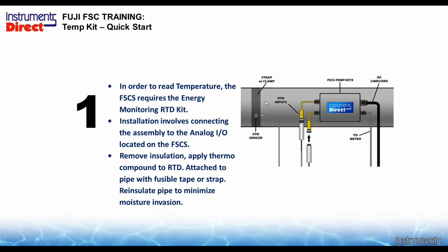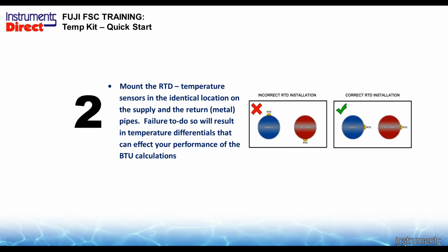So in this case here, we would give you the strap-on RTD, and then the thermo compound, kind of like a zinc oxide, to transfer this RTD temperature from the pipe surface itself for a metallic pipe application. And you put this on the pipe with a fusible tape. It's like a flexible duct tape that bonds to itself there, which stays there forever, or you can just use a hose clamp, whatever's convenient for you. So there's one on the supply, one on the return, and then the output signal from this device goes to your Portaflow-C in the analog input port. So we're now having the ability to log flow and temperature.